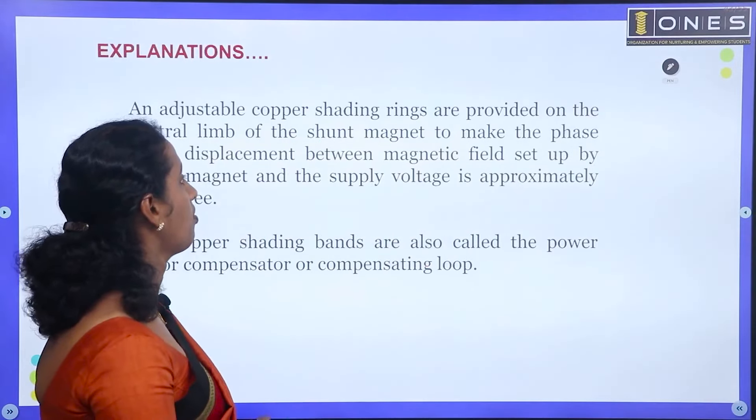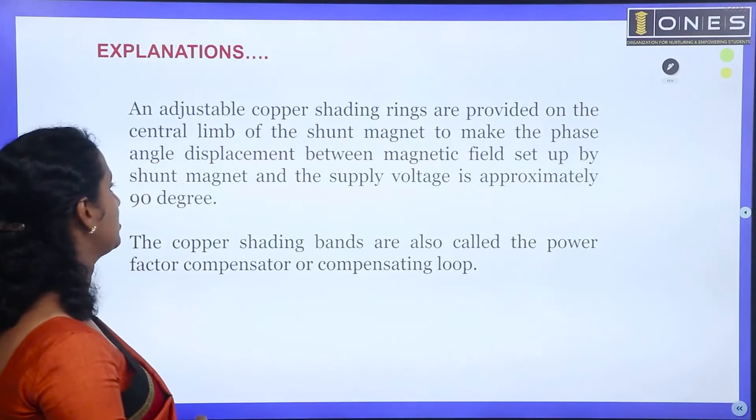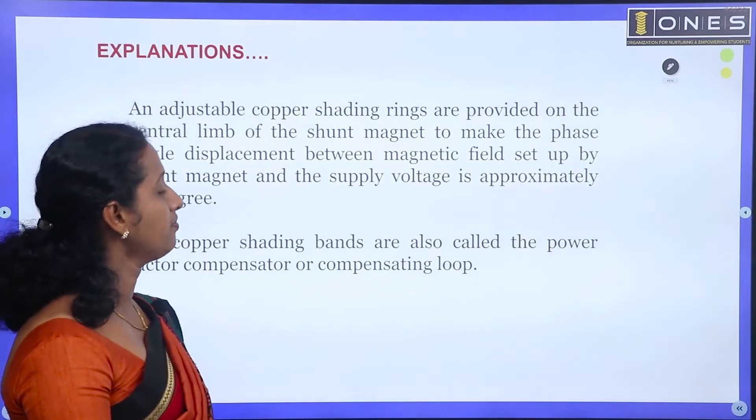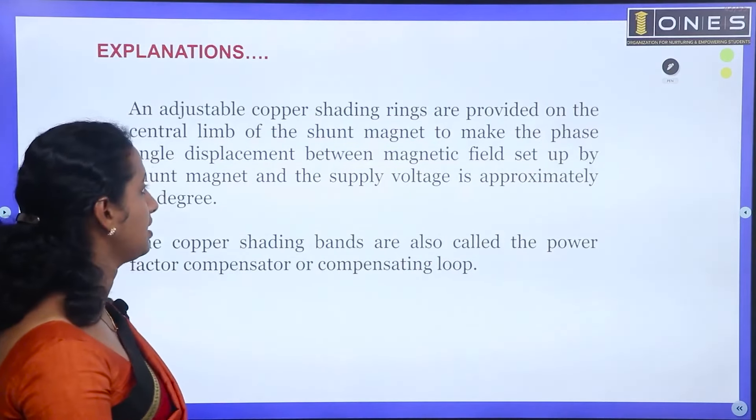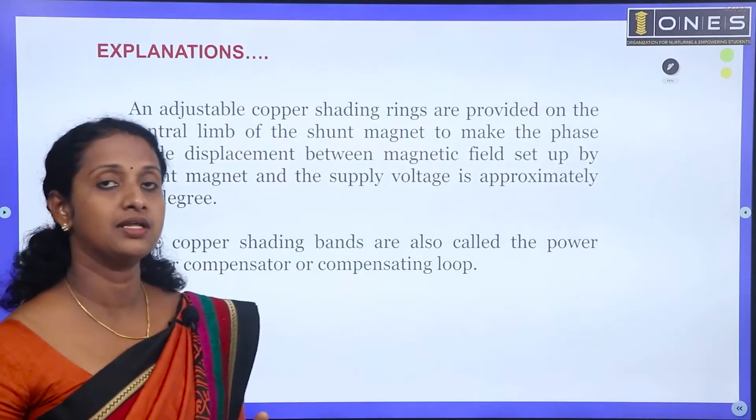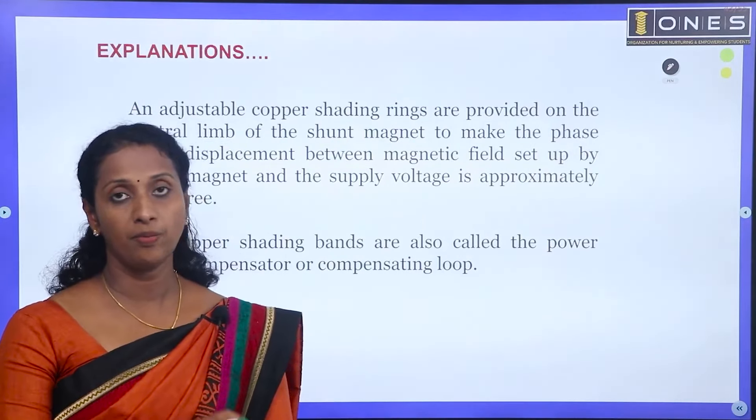Adjustable copper shading rings are provided on the central limb of the shunt magnet to make the phase angle displacement between magnetic field set up by the shunt magnet and the supply voltage approximately 90 degrees. The magnetic field angle is set at 90 degrees with the copper band.